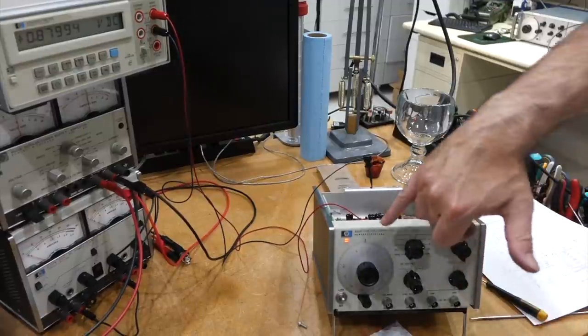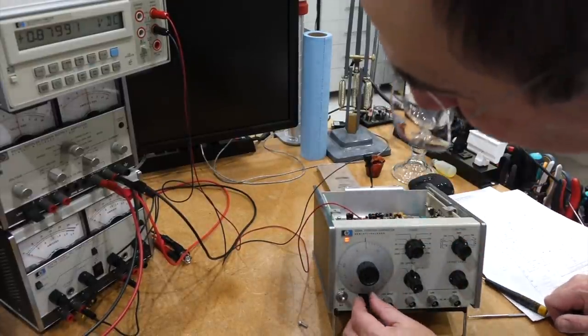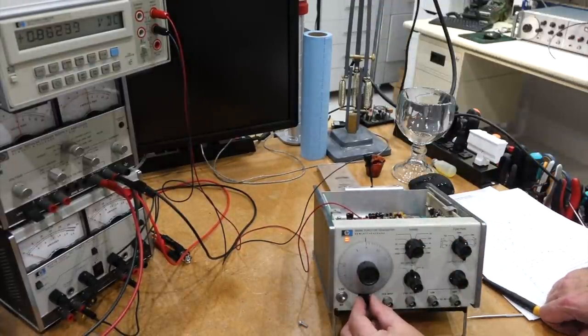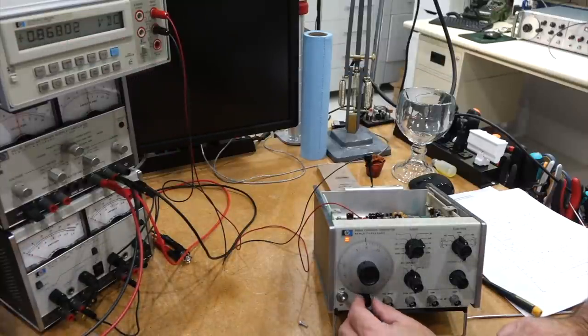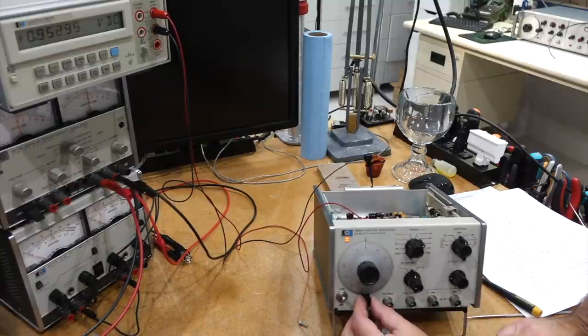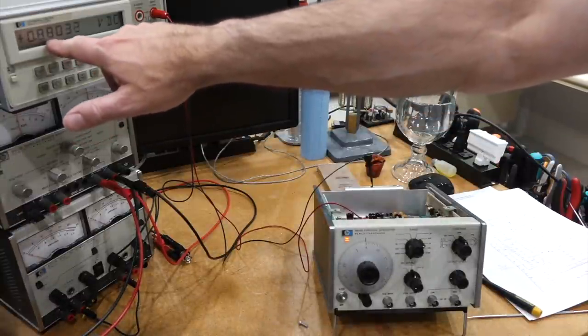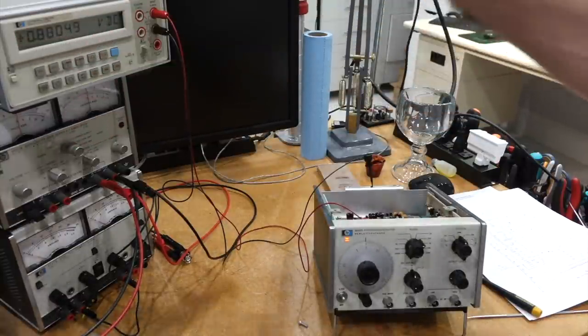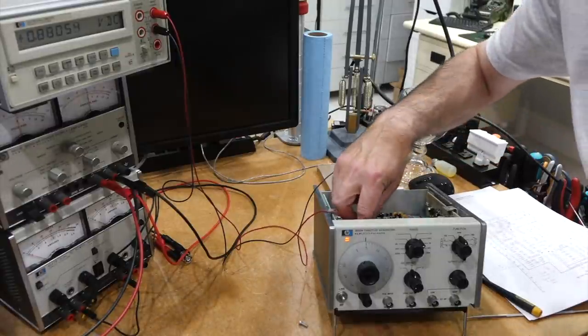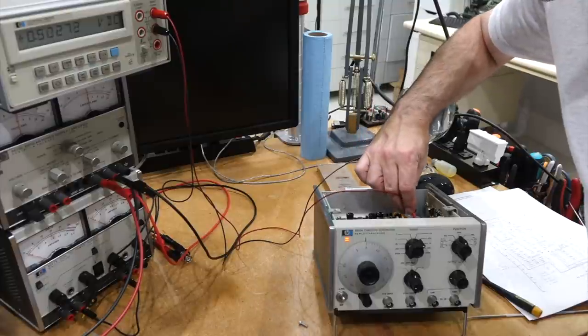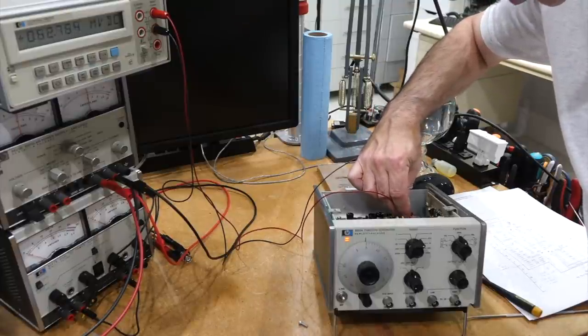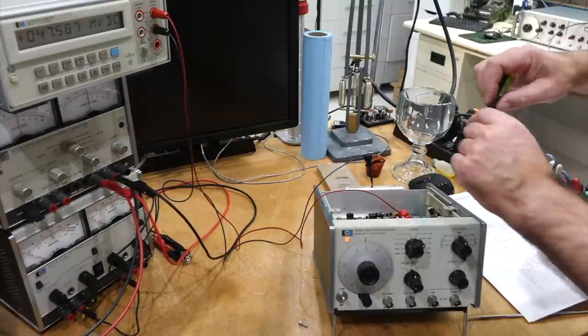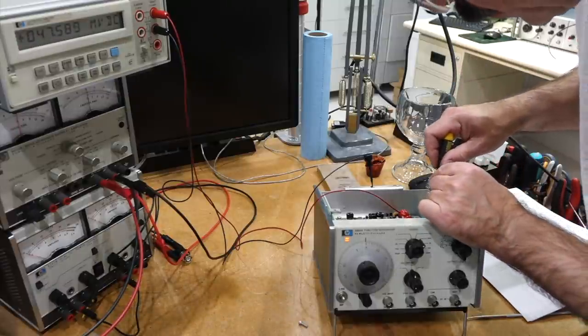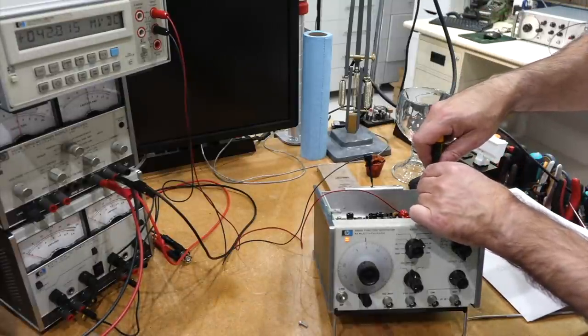That was annoying. You have to put the button mechanically so that when it's at 5, it's about at 900 millivolts, but that's super tough to do. So you get it at, I am, 0.880. And then there's another test point and you just correct for this 20 millivolts. So I am 20 millivolts off, so I need to be at minus 20 millivolts over here.